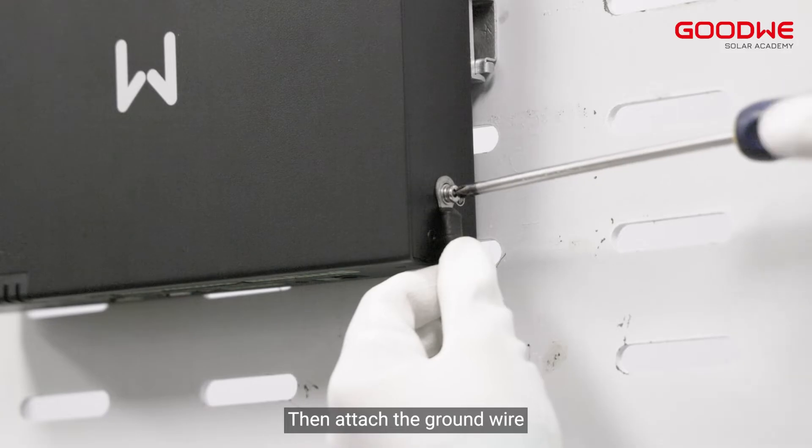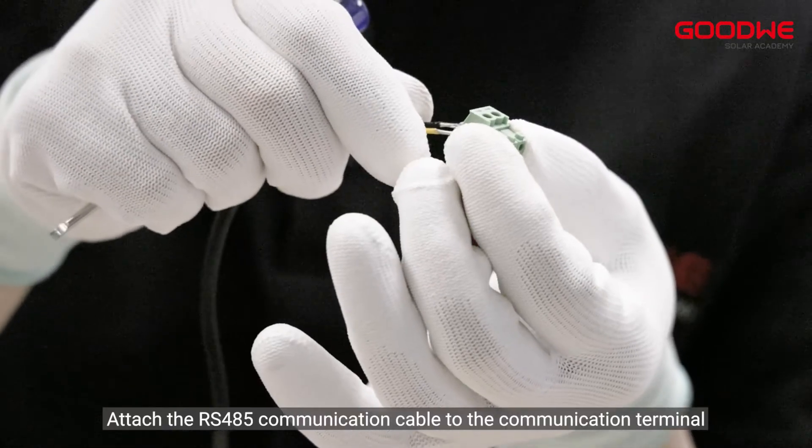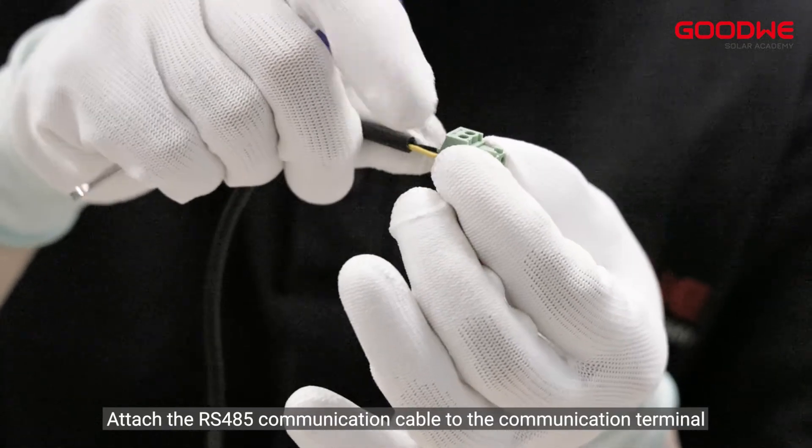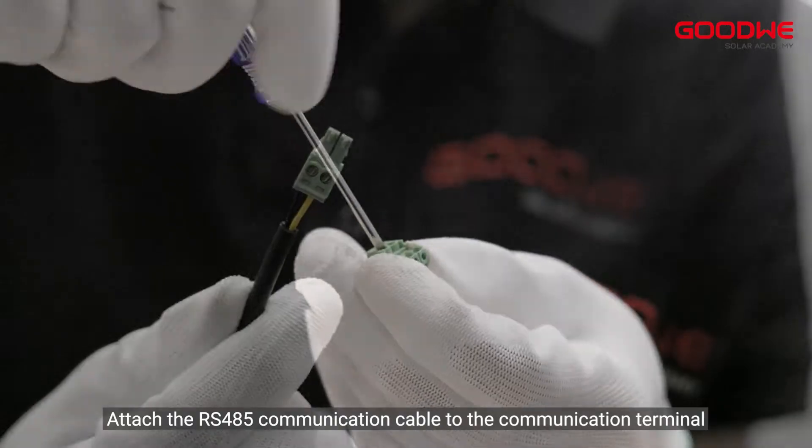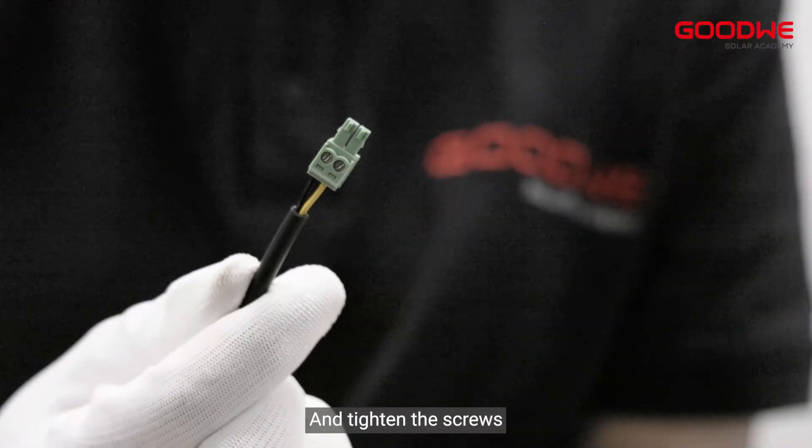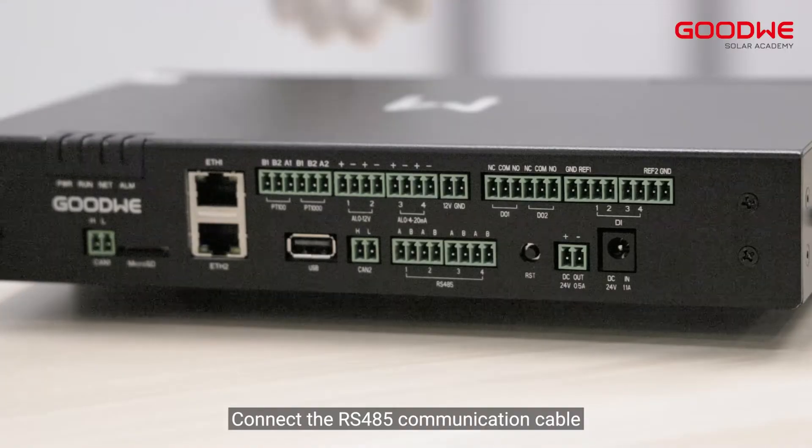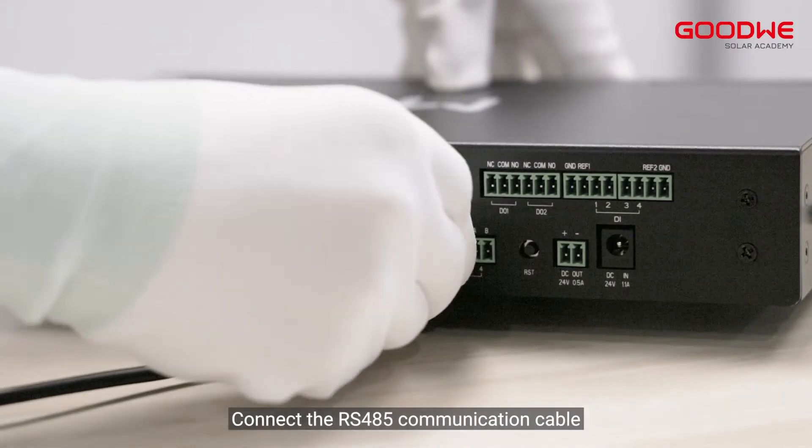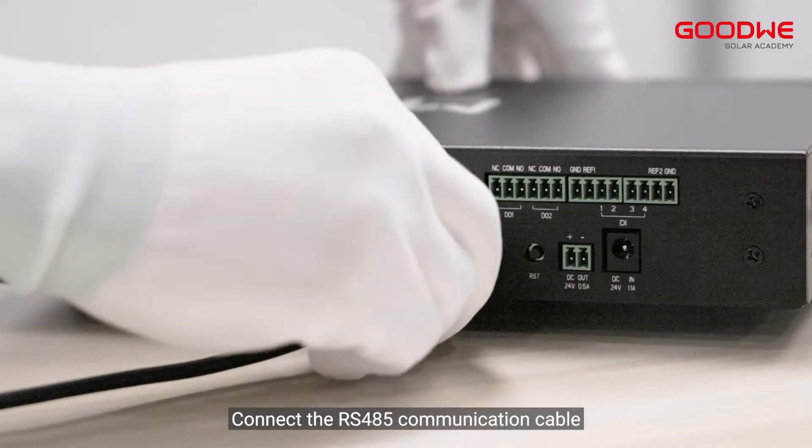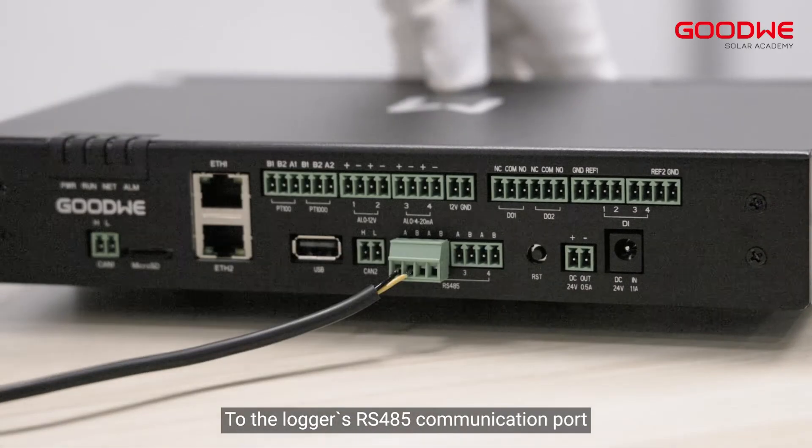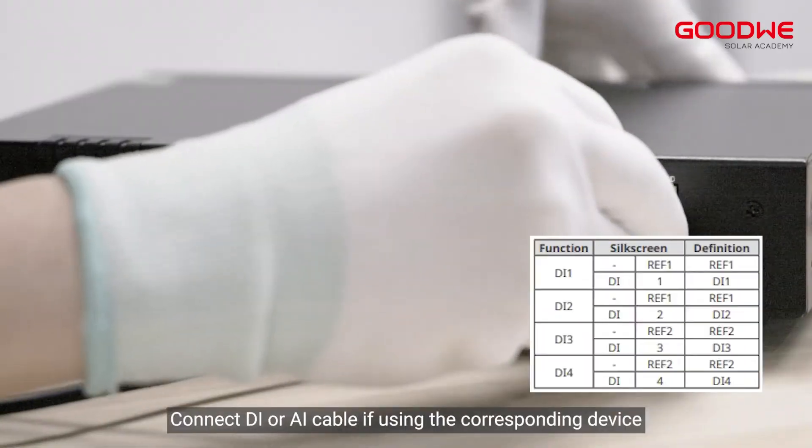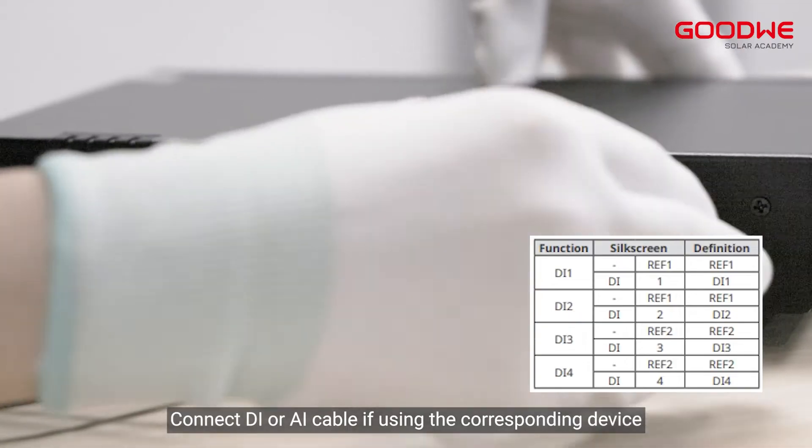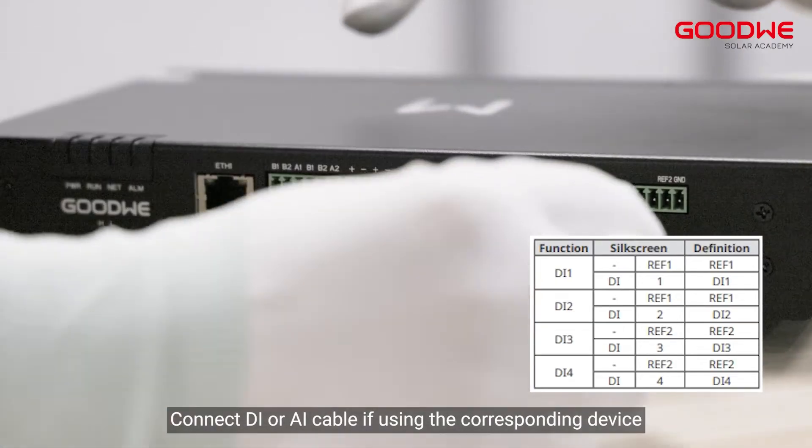Then attach the ground wire. Attach the RS485 communication cable to the communication terminal and tighten the screws. Connect the RS485 communication cable to the logger's RS485 communication port. Connect DI or AI cable if using the corresponding device.